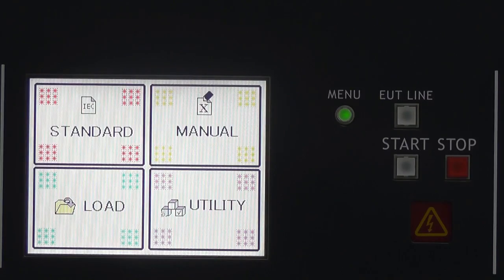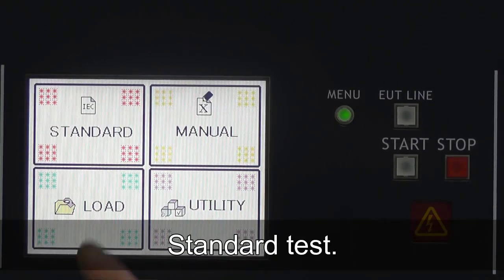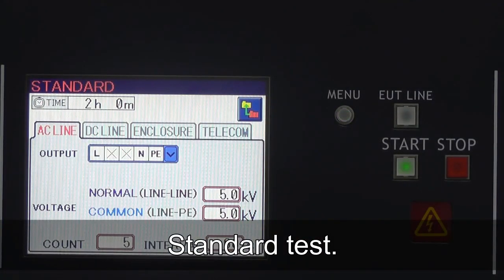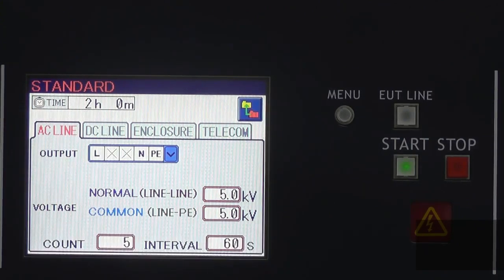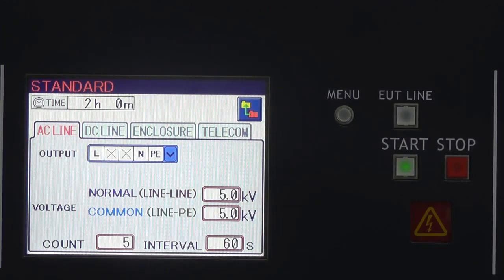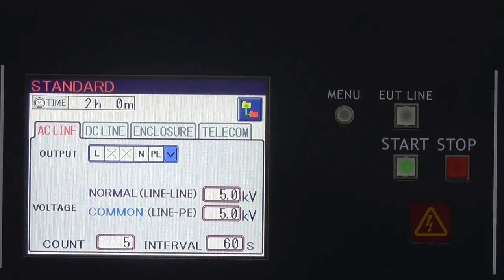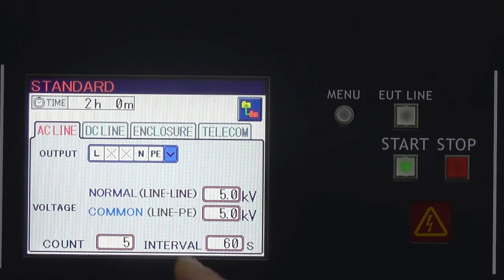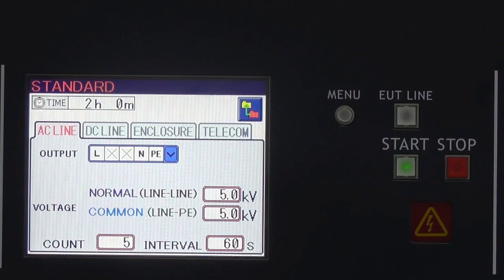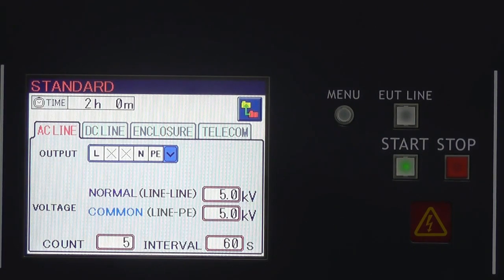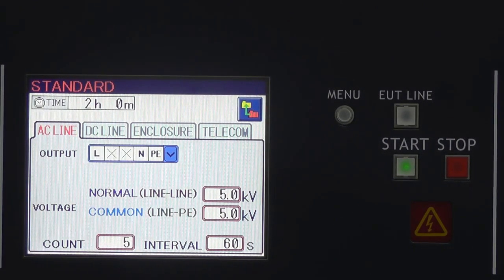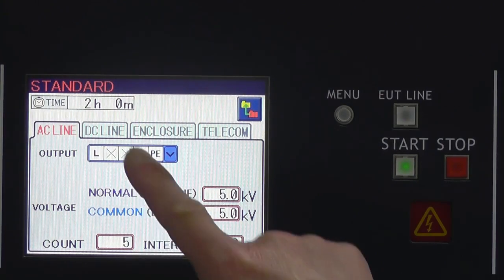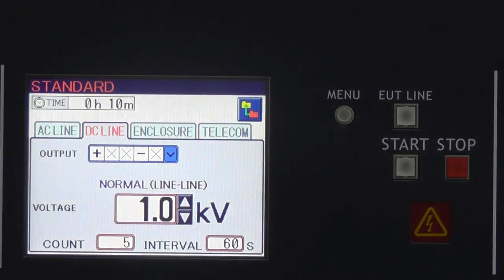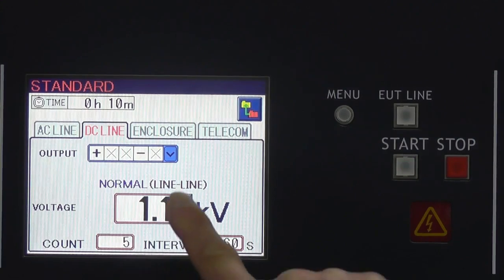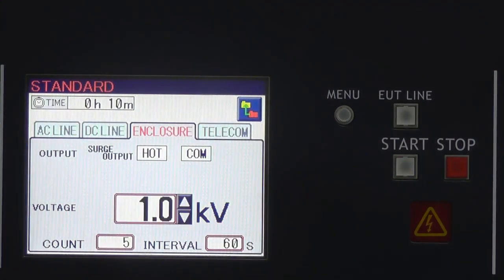Okay, let's go and see how to use each menu for the testing. In the standard test, the test conditions specified in the IEC 61000-4-5 standard are preset. Simply set the output destination and voltage according to the EUT line, and the test list will be automatically created.